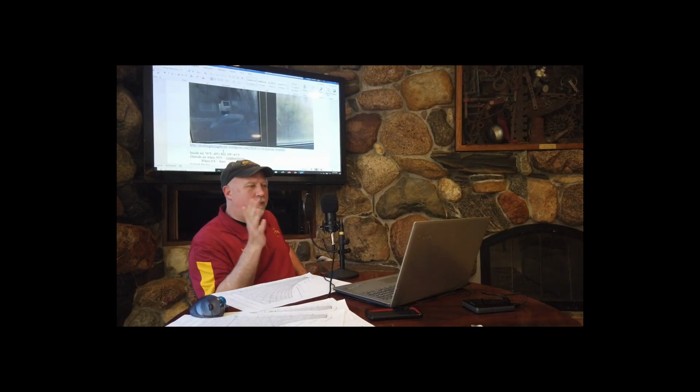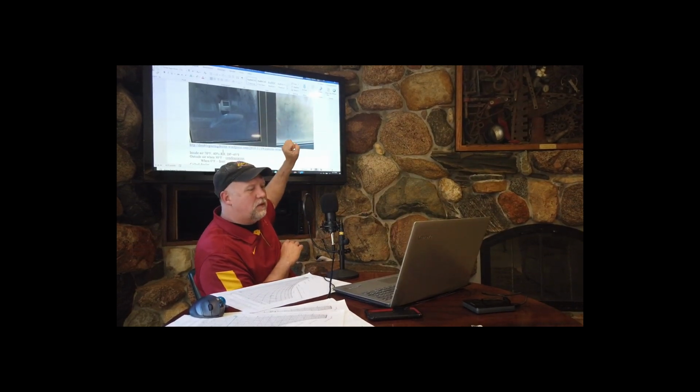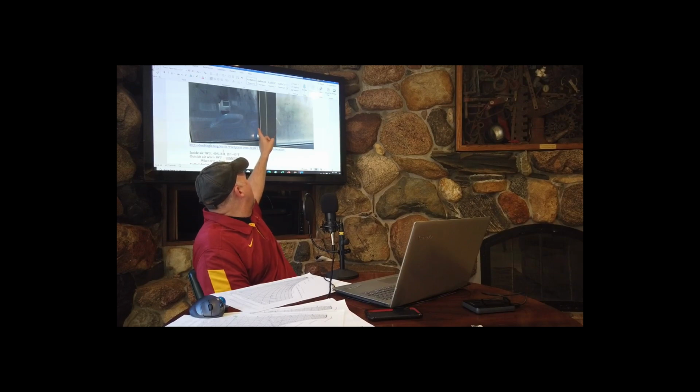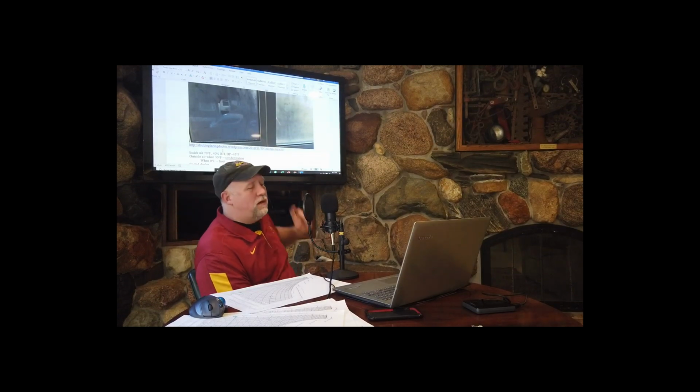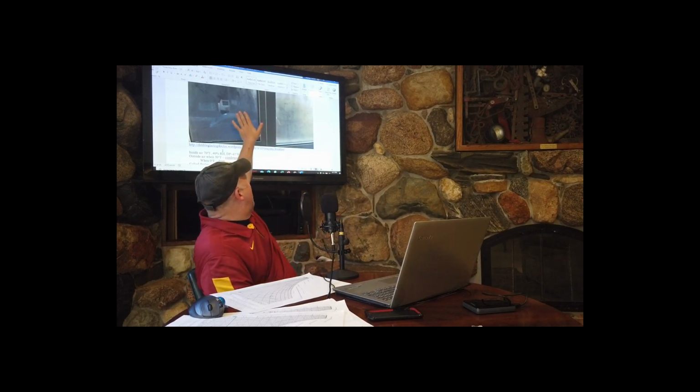Inside air is 70 degrees. All right, the average room temperature, somewhere in here, 70 degrees. Outside average temperature is 30 degrees. If condensation is occurring on this window edge, on the inside edge, that means that the inside edge of that window is 45 degrees Fahrenheit. 45 degrees Fahrenheit is closer to the outside air temperature than it is to the inside air temperature. And the outside air should be separated from the inside of this window by 2 panes of glass.